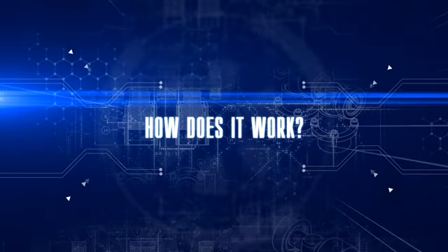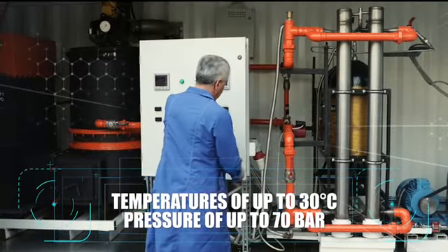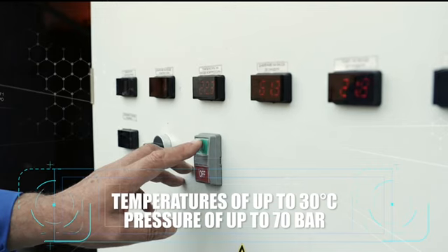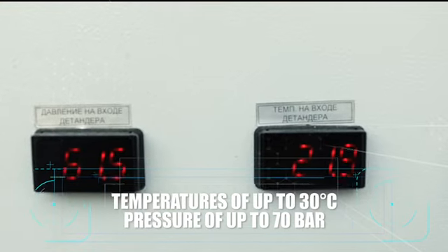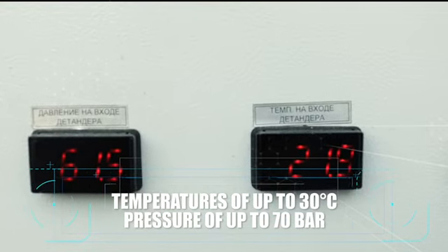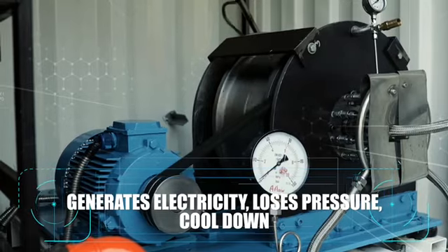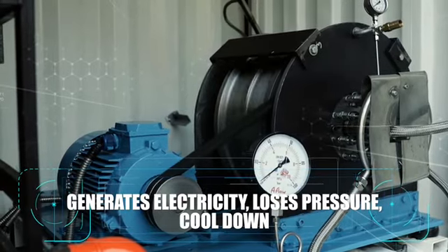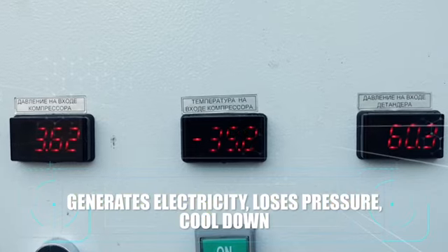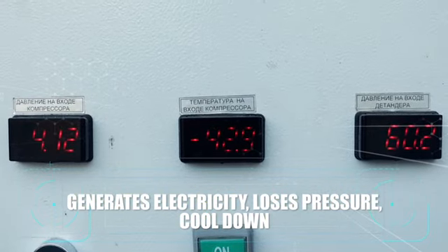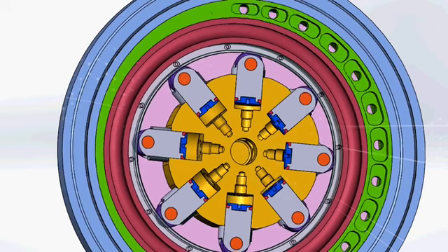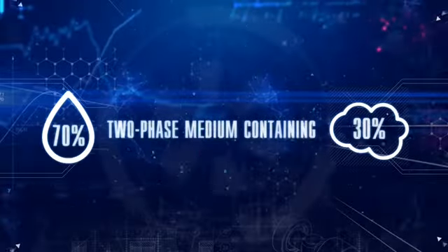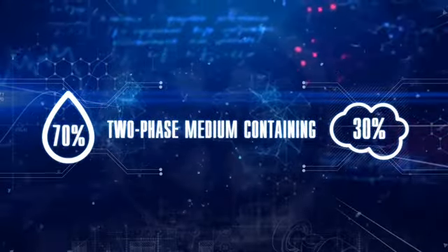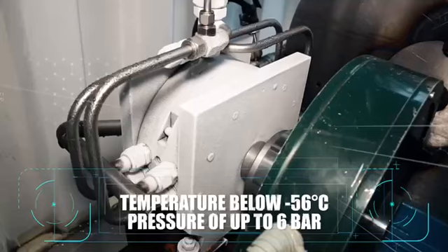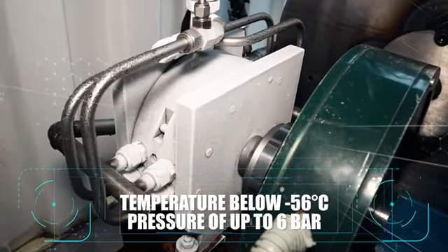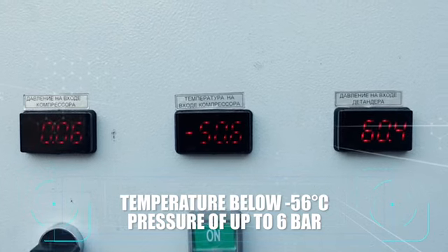How does it work? Liquid carbon dioxide is supplied to the turbine from an airtight tank, where it's held at temperatures of up to 30 degrees Celsius and pressure of up to 70 bar. In the turbine, the operating medium is expanded, generates electricity by rotating the rotor, and loses its pressure while cooling down. Carbon dioxide enters the compression pump as a two-phase medium, containing 70% liquid and 30% gas at a temperature below -56 Celsius, and pressure of up to 6 bar.